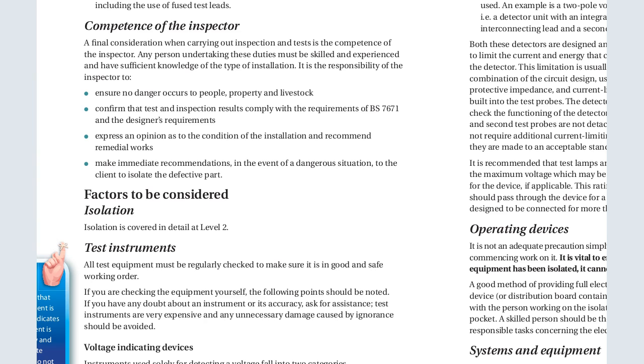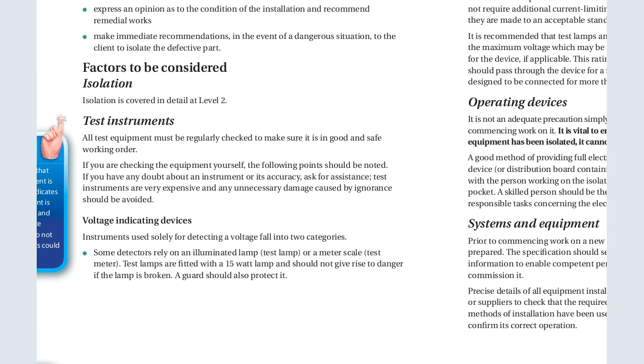So the final consideration when carrying out inspection and test is the competence of the inspector. Any person undertaking these duties must be skilled and experienced and have sufficient knowledge of the type of installation. It is the responsibility of the inspector, number one, to ensure no danger occurs to people, property, and livestock. Another one is to confirm that test and inspection results comply with the requirements. Another is to express an opinion as to the condition of the installation and recommend remedial work. Another is to make immediate recommendations to the client, in the event of a dangerous situation, to isolate the defective parts. Now, the factors to be considered.